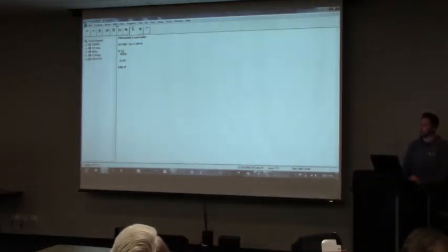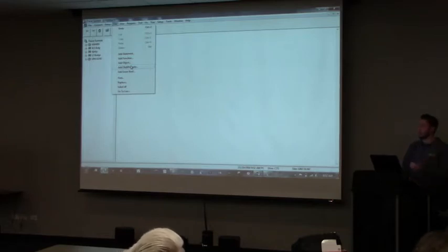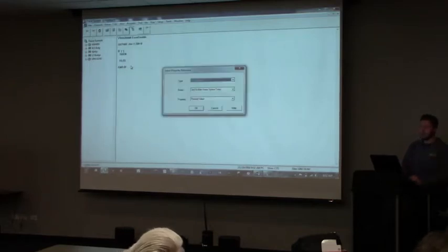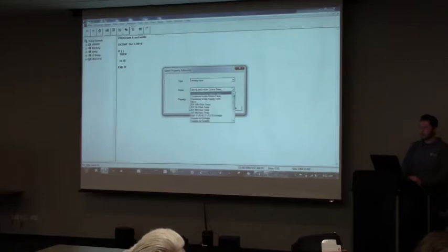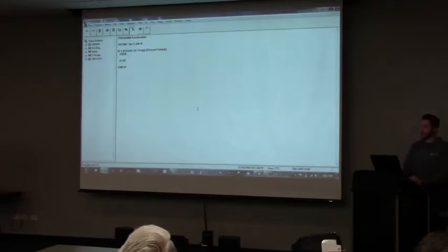So they already have an outside air temp sensor in this site. I'm just gonna go under Edit, and then I wanna add an object name and property. That way you can see the object name and the property of that object. So I'm gonna use analog input, and then they have the outside temperature right here. I already have it selected, so it popped up right there. So all I'm gonna do is use the less than statement, and I'm just gonna put 55, and now I have my argument already ready to go.